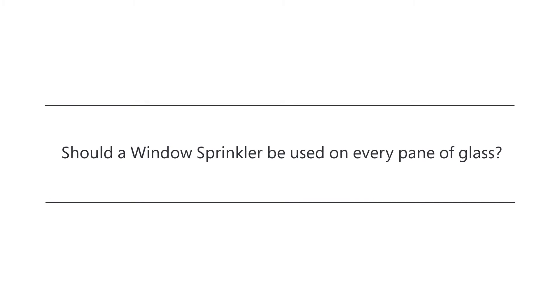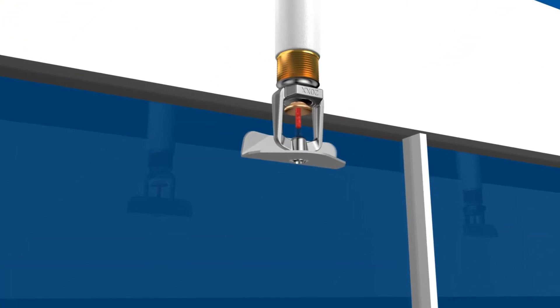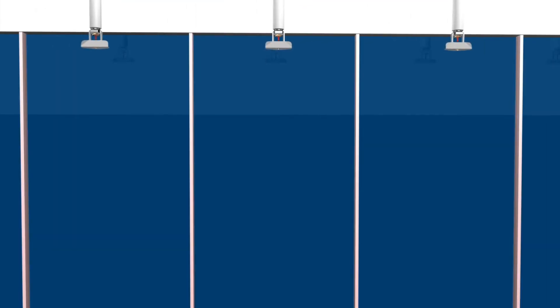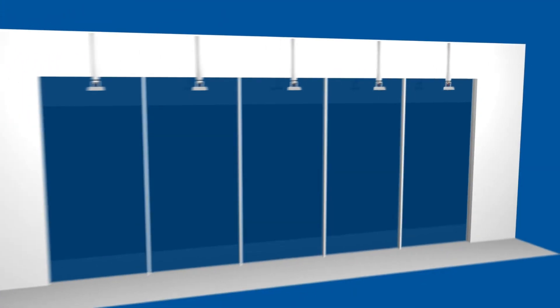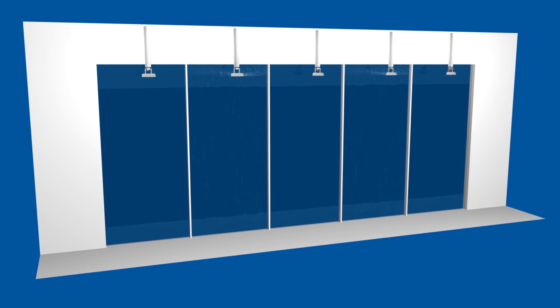Should a window sprinkler be used on every pane of glass? A window sprinkler is intended to be installed on each pane of glass if the pane is separated by a vertical mullion. The sprinkler's water distribution will stay within the vertical barriers and provide protection to that window only.